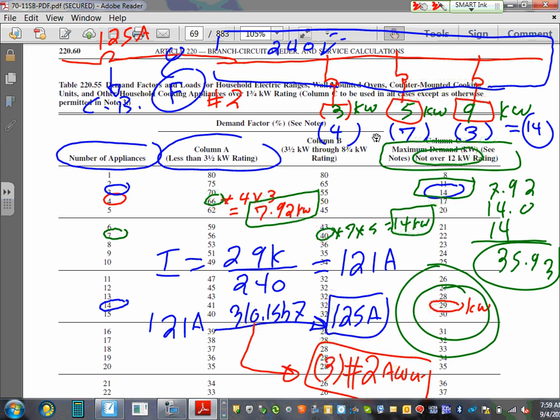So let me repeat this one because it has multiple things, guys. We have ranges under A, ranges under B, ranges under C. But C applies to all of them, because they're all listed at 12. So the first thing we do is for 14 of them, we find the demand under C. Then we apply A to the A, B to the B, C to the C, add them up, and see if we can come up with a smaller number than what we started with, which is the 29. If we do, then we use it. If we don't, then we're stuck with what we have. Any comments, any questions?